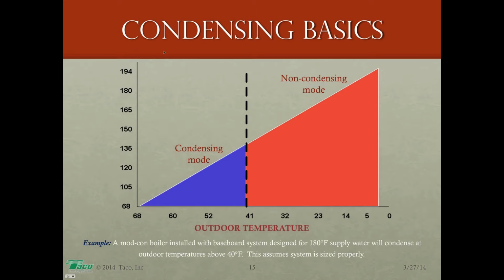system is sized properly. Again, just follow over here on the left you have water temperatures, okay? Down at the bottom you have outdoor temperatures, and you see as the temperature gets warmer, the boiler temperature will decrease until we reach the condensing point right here. That's the return water temperature condensing point. Anytime it's warmer than, let's say, 40 degrees out, that boiler will condense. Now, how much of the time will that happen? If you look at it here, it doesn't look like a whole lot of time.